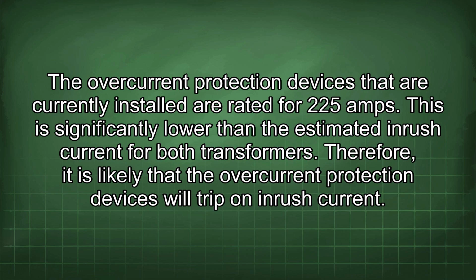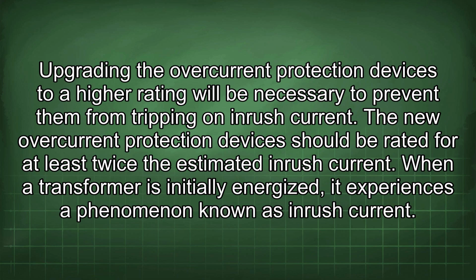This is significantly lower than the estimated inrush current for both transformers. Therefore, it is likely that the overcurrent protection devices will trip on inrush current. Upgrading the overcurrent protection devices to a higher rating will be necessary to prevent them from tripping on inrush current. The new overcurrent protection devices should be rated for at least twice the estimated inrush current.